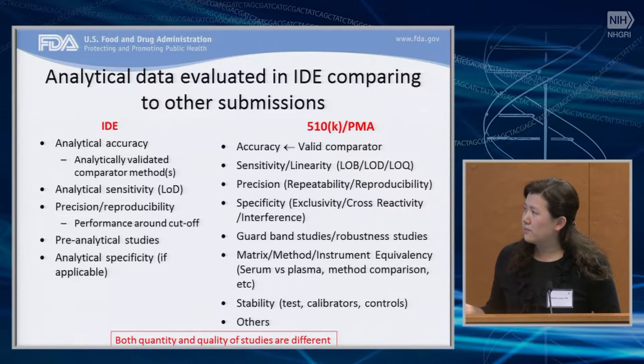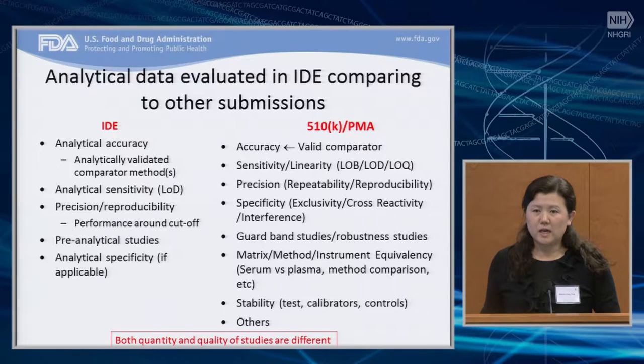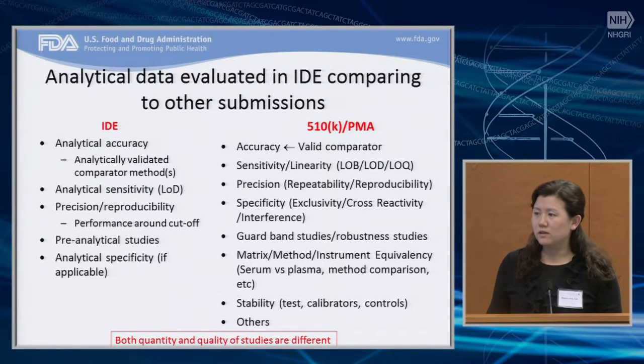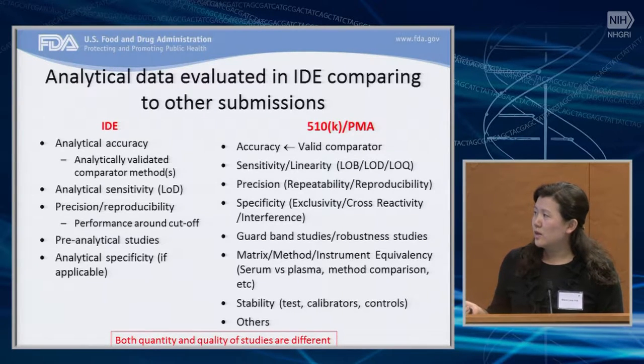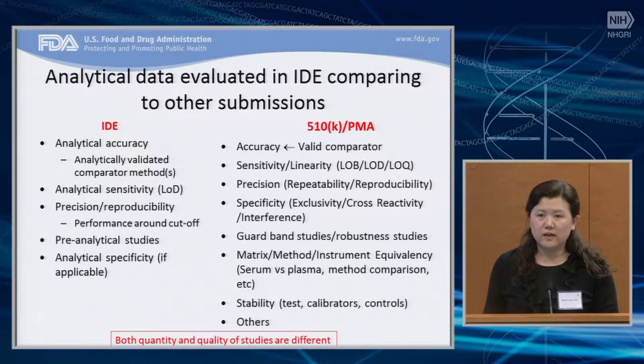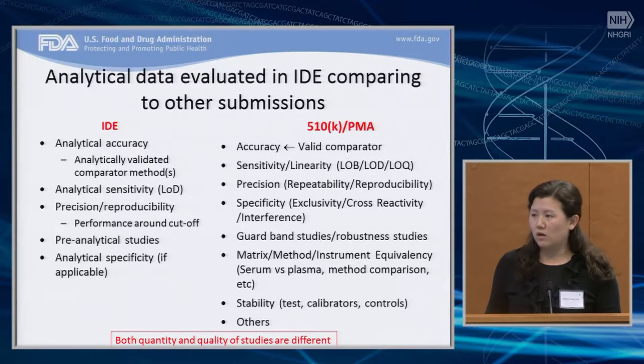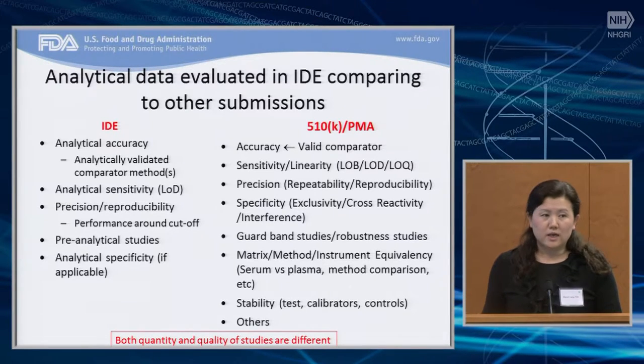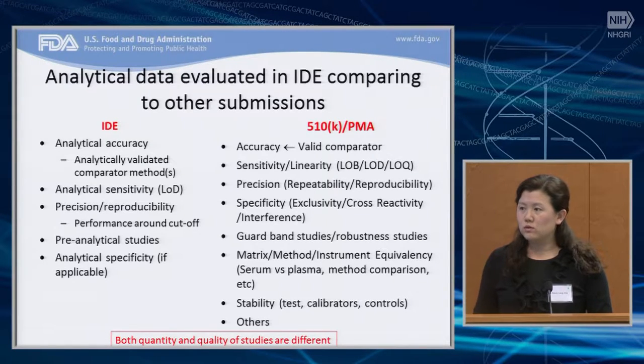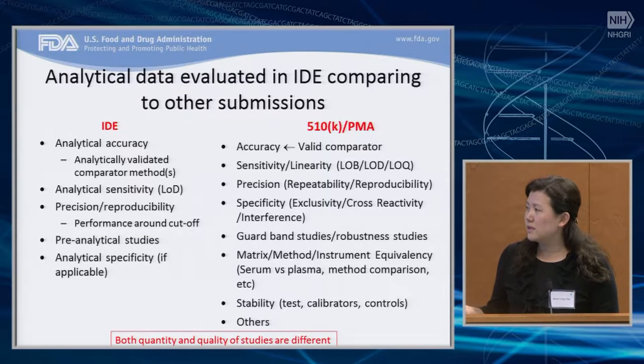When you conduct the IDE studies, there will be challenges. In the accuracy studies, there may be a lack of comparator method or reference method, but normally we accept an analytically validated comparator method. If you can justify why the reference method is not available and why the comparator method is validated and appropriate, you can discuss this through the pre-submission process and we will give you comments and suggestions. For the precision study, it's important to use samples around the cutoff because we want to see performance for those difficult-to-test samples near the cutoff regions.